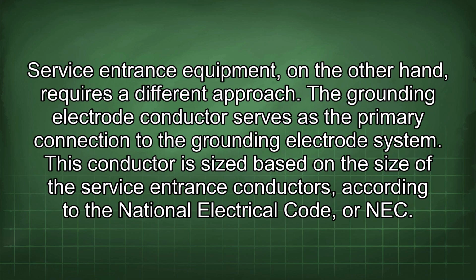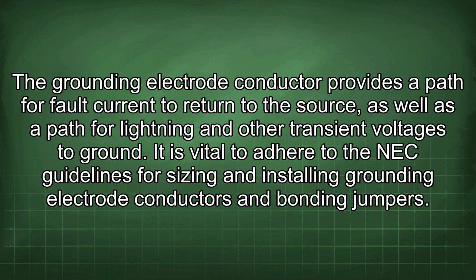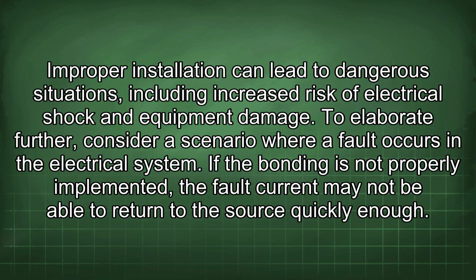Service entrance equipment, on the other hand, requires a different approach. The grounding electrode conductor serves as the primary connection to the grounding electrode system. This conductor is sized based on the size of the service entrance conductors according to the National Electrical Code, or NEC. The grounding electrode conductor provides a path for fault current to return to the source, as well as a path for lightning and other transient voltages to ground. It is vital to adhere to the NEC guidelines for sizing and installing grounding electrode conductors and bonding jumpers. An improper installation can lead to dangerous situations, including increased risk of electrical shock and equipment damage.